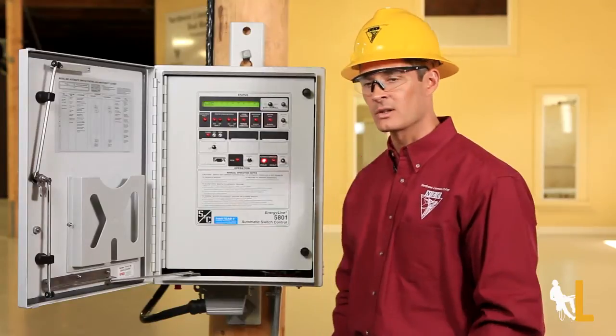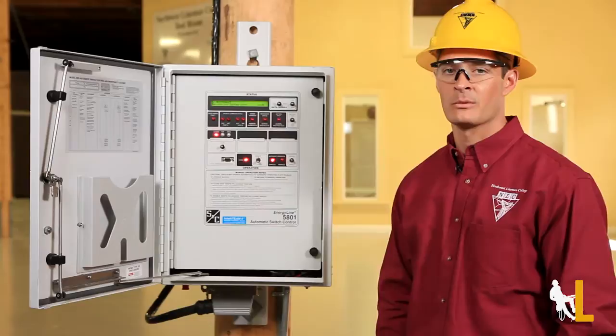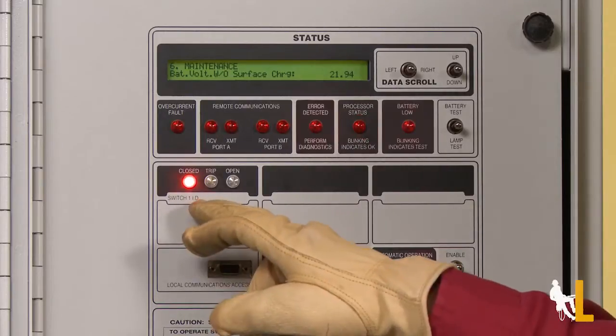To open the line switch, first flip this down to local. This will disable SCADA and prevent it from operating remotely. Then toggle this switch to open.